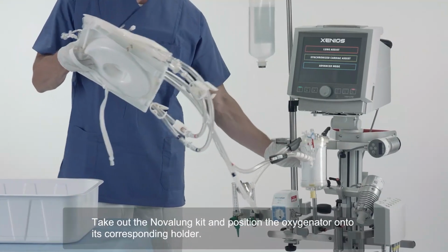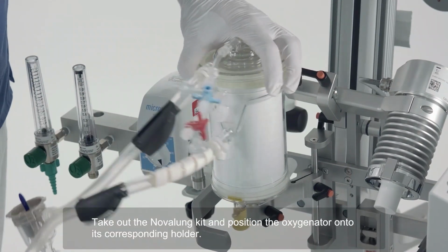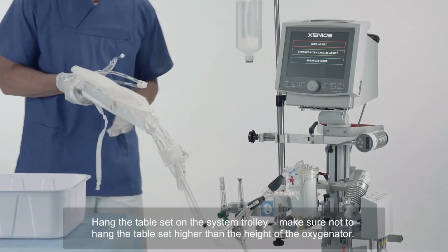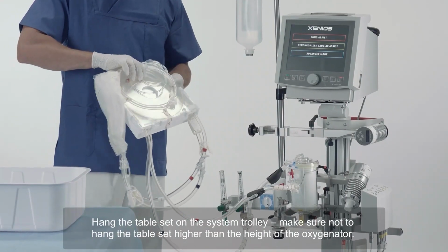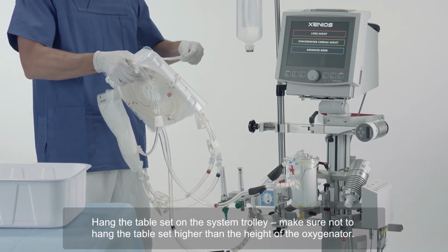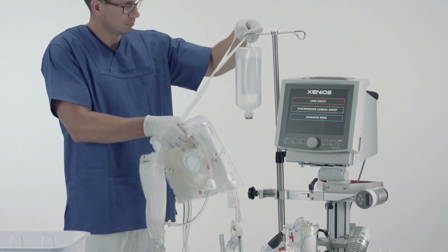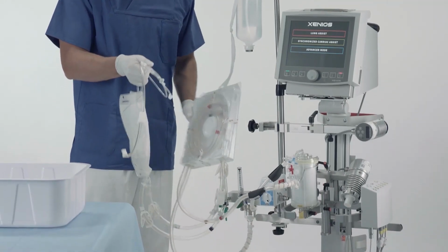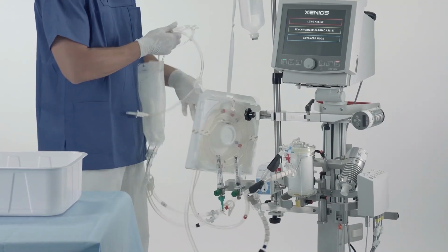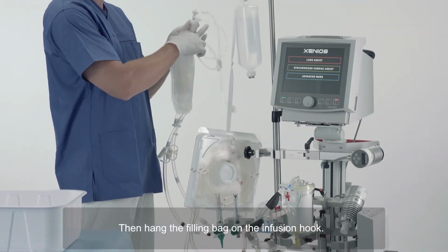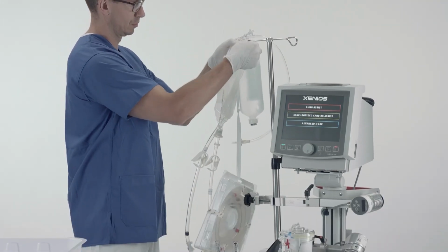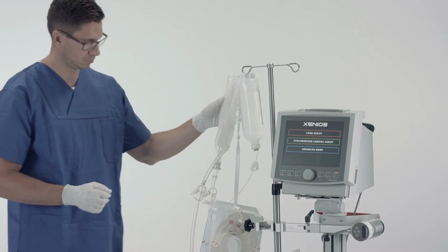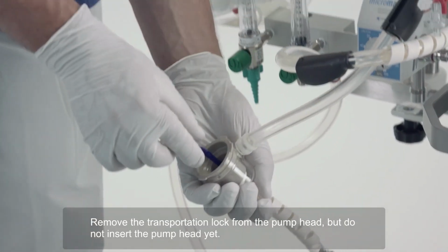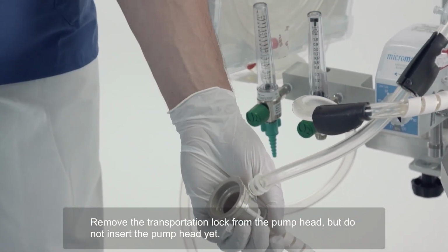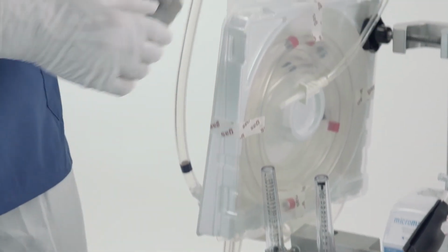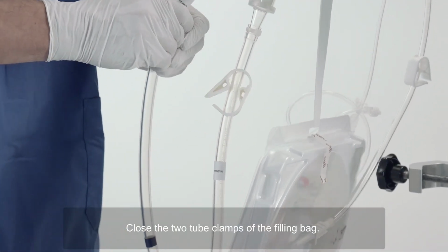Take out the Novalung kit and position the oxygenator onto its corresponding holder. Hang the table set on the system trolley. Make sure not to hang the table set higher than the height of the oxygenator. Then hang the filling bag on the infusion hook. Remove the transportation lock from the pump head, but do not insert the pump head yet. Close the 2 tube clamps of the filling bag.